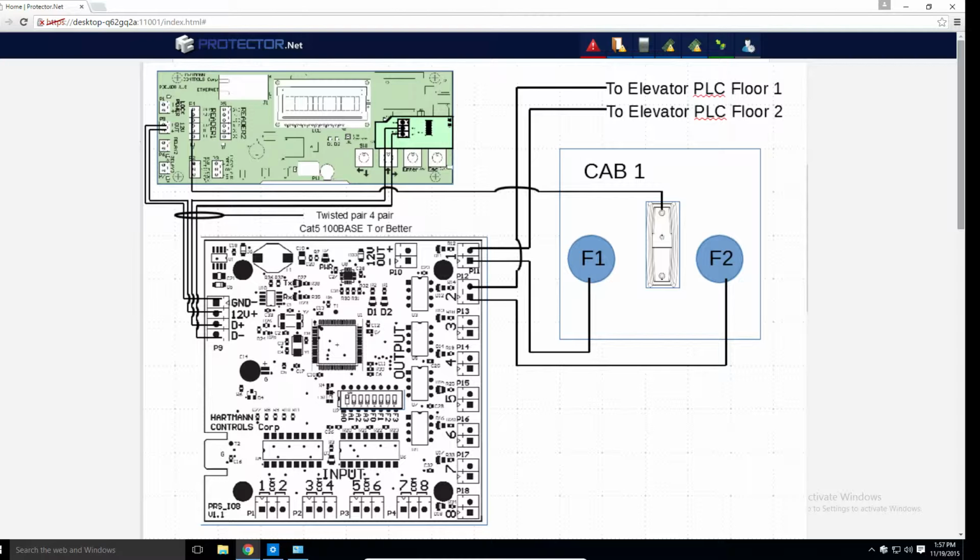Our system supports button sensing and non-button sensing elevator technology. Non-button sensing, seen in the display diagram, is when the floor buttons in the cab go through our relays before going to the elevator system. When a user presents a credential to the cab, a master controller will activate any relays that correspond to the floors that cardholder should have access to. The cardholder now pushes a button for a floor, which will go through our relay and to the elevator system. The main disadvantage of non-button sensing is that we can't see which floor was selected.